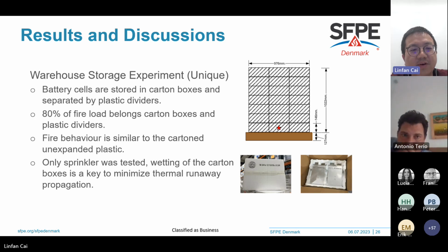Therefore, for this categorization, sprinklers are recommended by, I believe, most local regulations for sprinkler requirements, so only sprinklers were tested. Also, a key finding is that wetting the carton boxes is the key measure to minimize thermal runaway propagation for the warehouse cases.